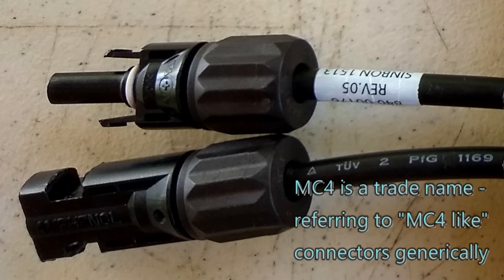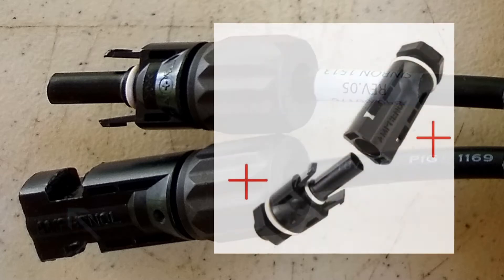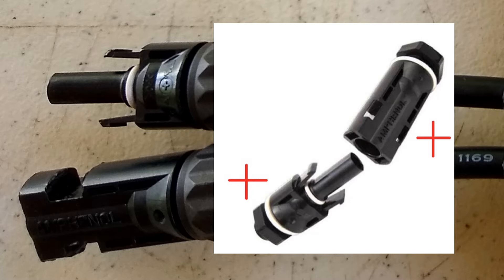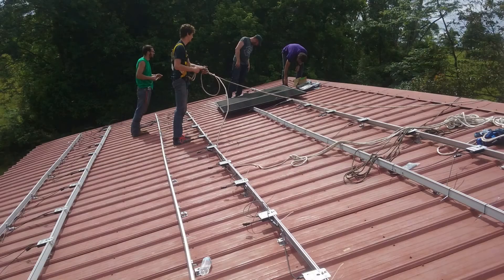Usually that's going to be from the solar panel or the optimizer, connecting down to a junction box or a combiner box. When a solar panel comes pre-terminated with MC4s, the female connector end is connected to the positive conductor and the male is connected to the negative. Just remember when you're making a jumper it's going to be the opposite, because you're going to have to connect the female connector to that male, and that will still be the positive lead.